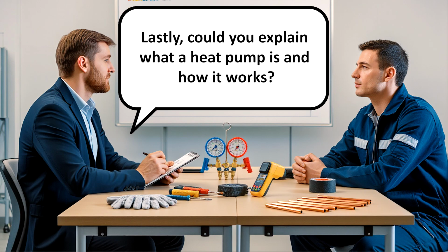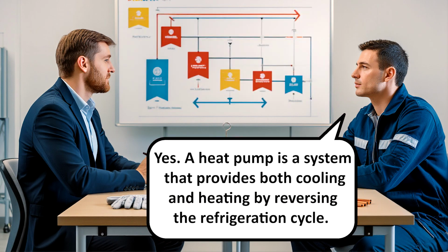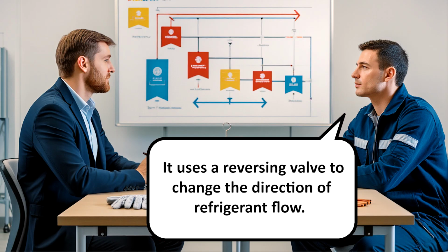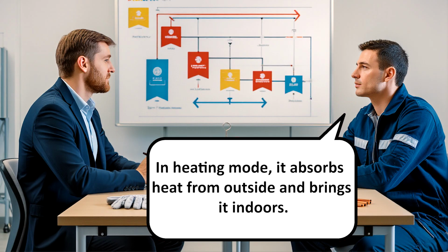Lastly, could you explain what a heat pump is and how it works? Yes, a heat pump is a system that provides both cooling and heating by reversing the refrigeration cycle. It uses a reversing valve to change the direction of refrigerant flow. In heating mode, it absorbs heat from outside and brings it indoors.